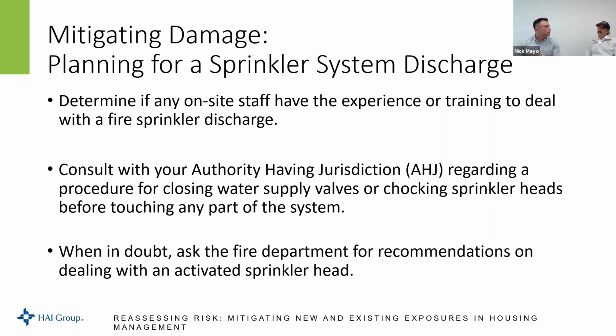Paul, can you give a little perspective on, let's say, if someone had the knowledge, experience, and training to deal with an activated sprinkler head, would a fire marshal be comfortable with closing an isolation valve of a sprinkler system for a particular floor? A lot of that depends on the area of the country you're in. Where we're in Middletown, I know that we would have no problem coming out to the building, meeting the person, and having them walk us through the process of what they're going to do. We're okay with it because we understand what's at stake with the water damage, what have you.